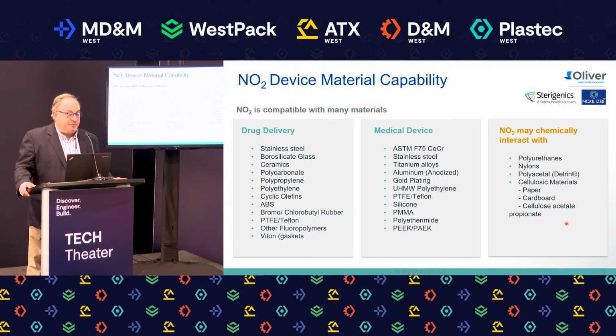The next question that typically is asked about NO2 is materials compatibility. As I stated earlier in the presentation, no one sterilant is good for all materials. So for NO2, where we are strong is in the area of this column here, followed by, for medical devices, these materials. The materials where we have some trouble, and Jeremy's going to show you some of the results, deal with nylons and polyurethanes, as well as polyacetal, which is your Delrin, and cellulosics, uncoated. Paper materials, if exposed to NO2, end up just basically falling apart if they're not coated beforehand going into the process. And again, cellulose acetate is another challenging material for the process.